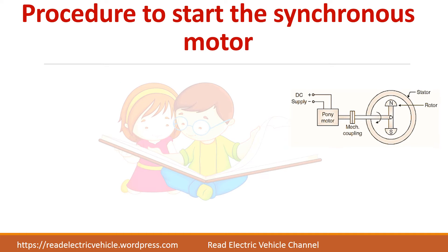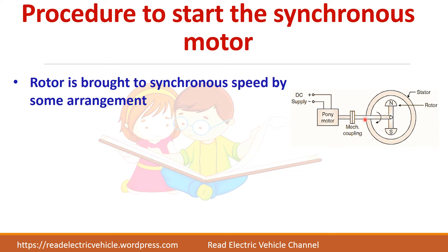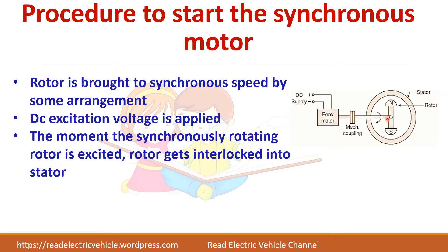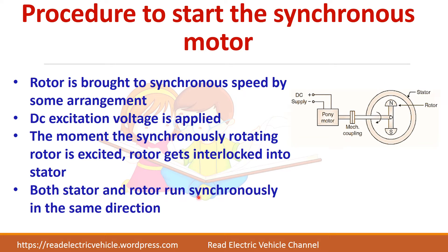What is the procedure to start the synchronous motor? First, bring the rotor to synchronous speed by some arrangement. Then give DC supply for the field winding so that it will get north and south polarity. Once DC voltage is given, the north pole of the rotor and south pole of the stator get locked together, because both are rotating at synchronous speed. So both rotor and stator run at synchronous speed in the same direction.